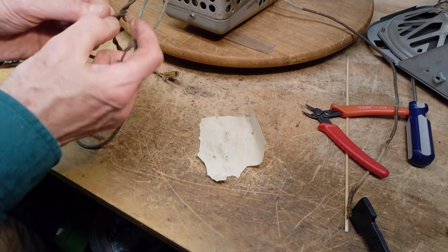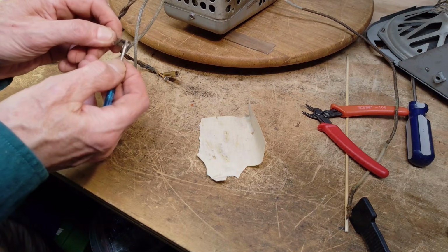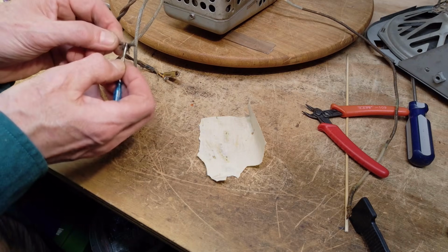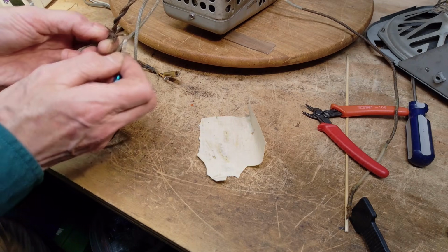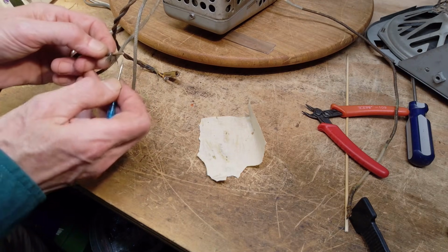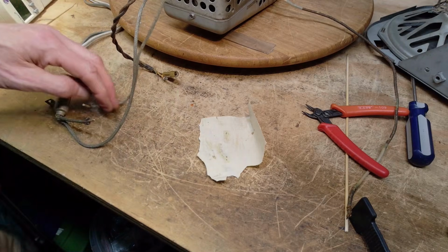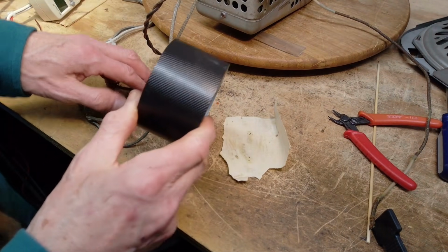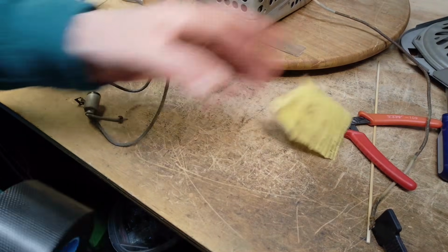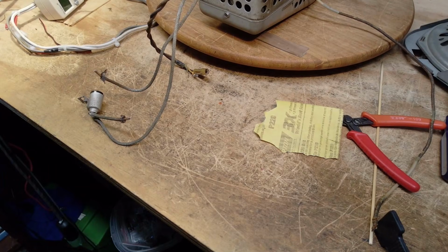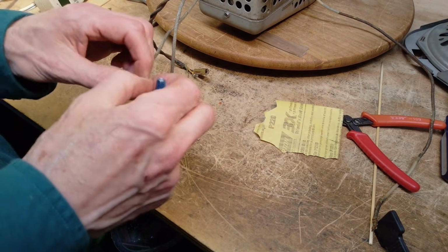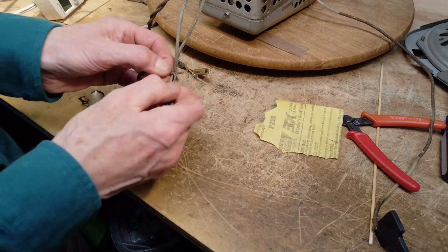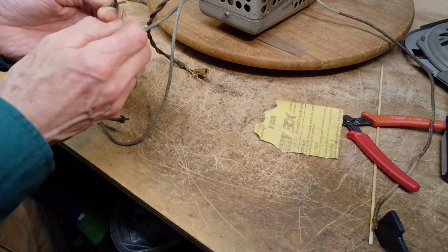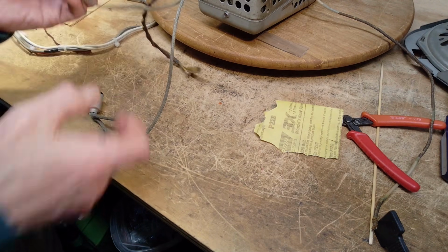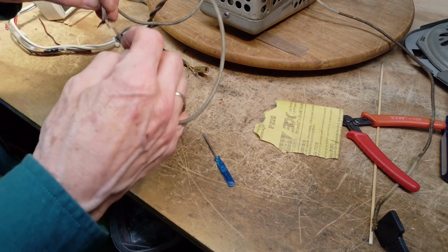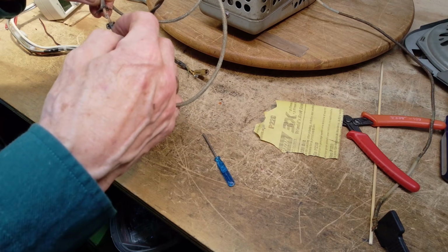So the conductor is 8,000 volts through the insulation to this lead sheath. It's a little more complicated than that, but with paper insulating it - wraps of paper, like picture paper, about this kind of width, just regular paper. Well, it's not brown, but paper that has been washed and cleaned so it's got no ions in it, nothing conductive left in it. In the process of making paper, don't they use acid and all kinds of stuff? So it's tricky to clean the paper enough that you can use it in a power cable. But this is what was figured out pretty early on.